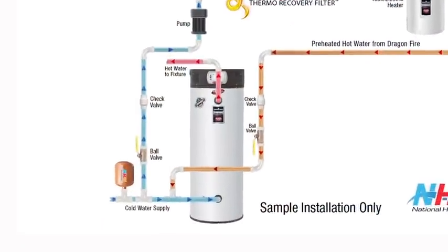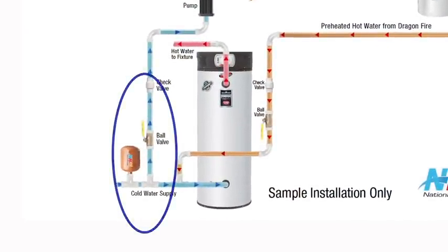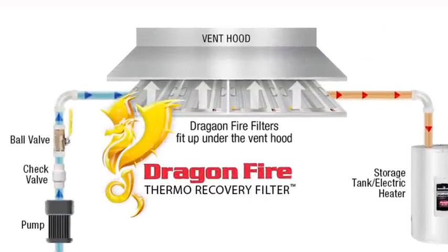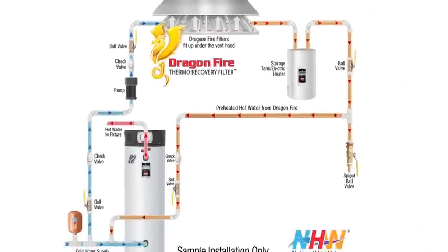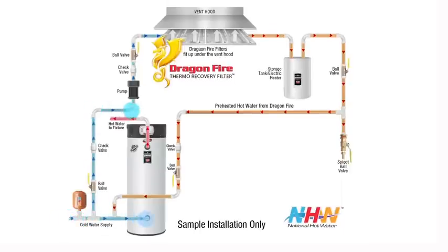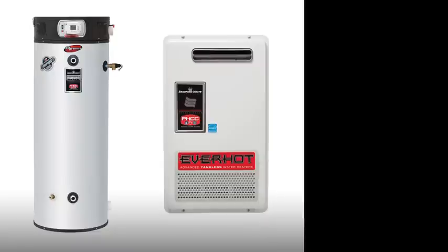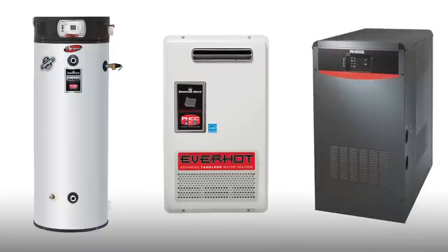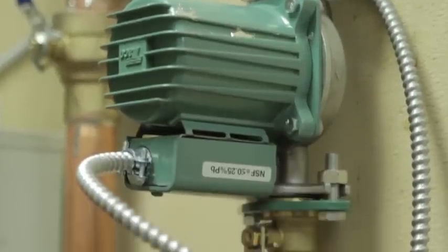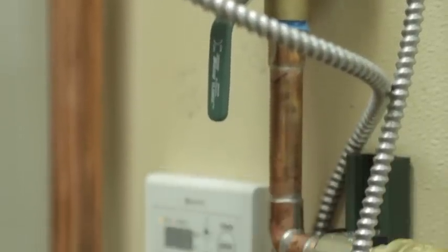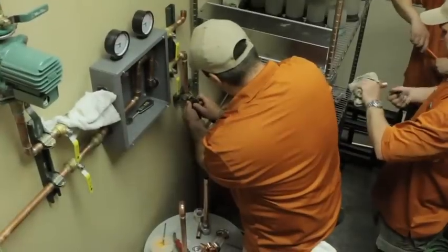Our plumber begins by adjusting the piping to route a portion of the incoming water supply to the Dragonfire filters. Connecting the Dragonfire filters with the water coming into the building and the existing water heater will supply Dragonfire with water to heat and a way to send that heated water to the water heater. Dragonfire filters can be used with tank-type water heaters, instantaneous water heaters, and boilers. Now, a circulating pump is installed. This pump pushes the water through the Dragonfire filters and onto the water heater.